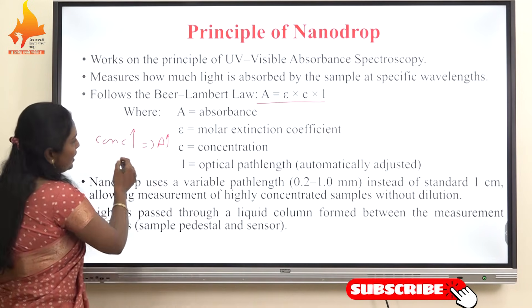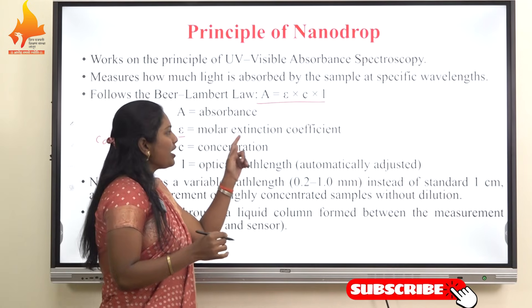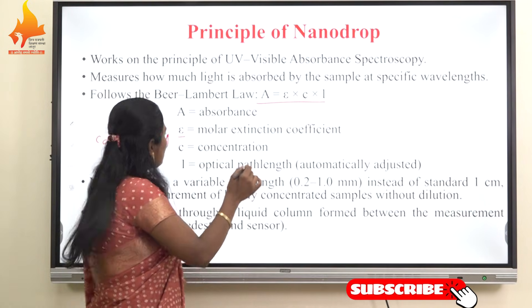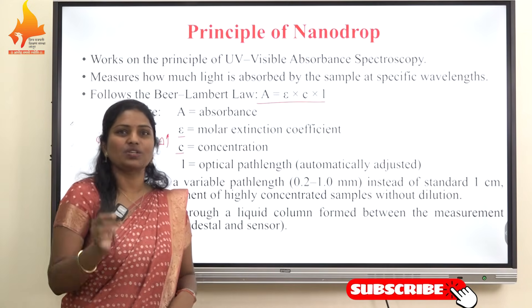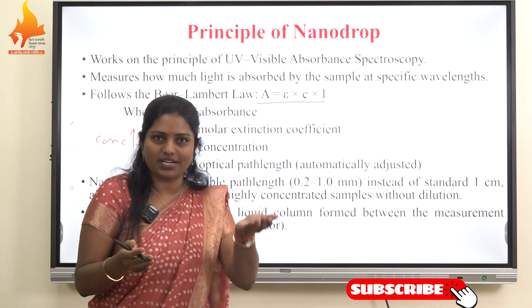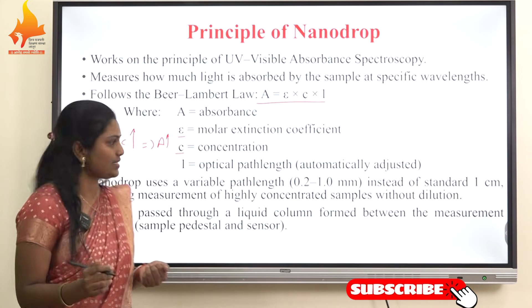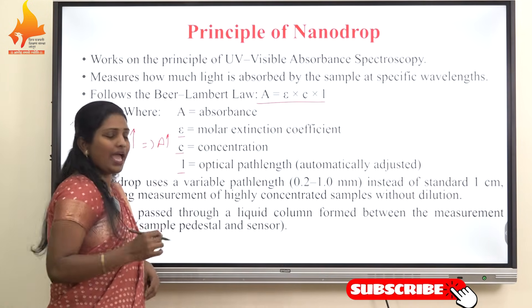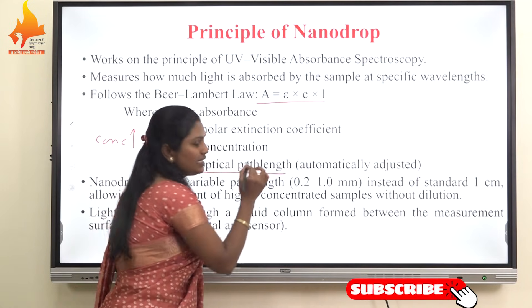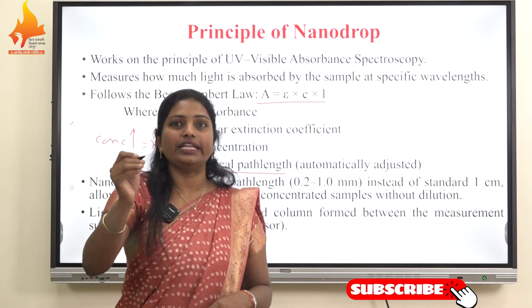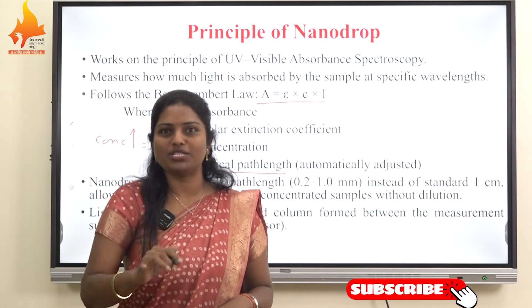In the Beer-Lambert equation, epsilon (ε) is the molar extinction coefficient. C is the concentration — as concentration increases, absorbance of the sample increases. L is the optical path length, which is automatically adjusted in the nanodrop technique, enabling accurate measurement of concentrated samples without dilution.